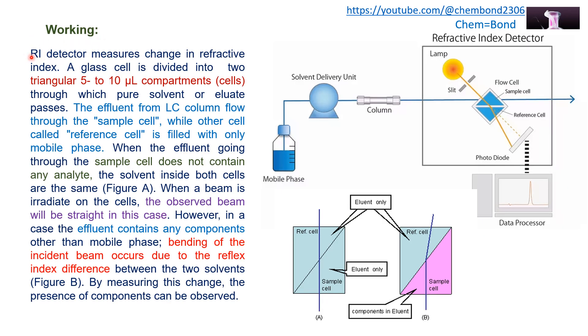The refractive index detector measures the change in refractive index. A glass cell is divided into two triangular 5 to 10 microliter compartments through which the pure solvent and the eluate pass. One compartment is the reference cell and the other is the sample cell. The effluent from the LC column flows through the sample cell, while the reference cell is filled with only the mobile phase. When the effluent going through the sample cell does not contain any analytes, the conditions inside both cells are the same, as shown in Figure A.